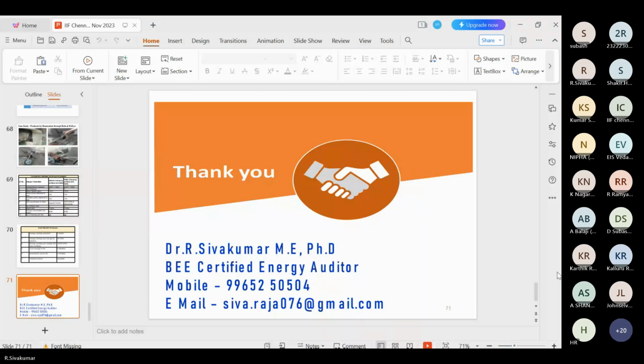Yes, sir. Recently, last week, I did one baseline audit in a steel industry in the Erode area. They are adapting a brand new 24 pulse IGBT rectifier. 10 ton is the crucible capacity. The furnace power capacity is almost 4,000 kilowatt. They have a pakka setup with poking mechanism and other things. They take only 620 units because they use very low grade steel waste, all scrap based. Sponge iron is used for only 10 to 15%. Even so, with that raw material they achieve 620.